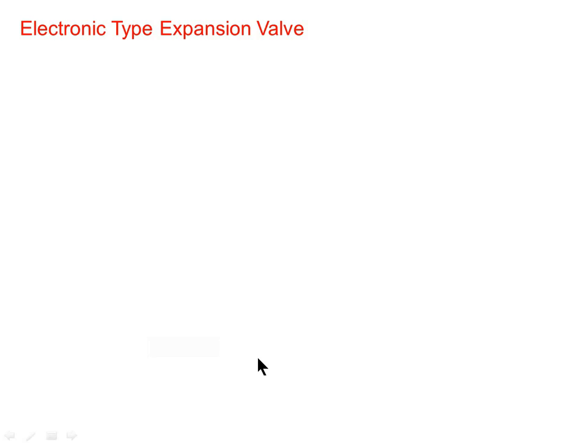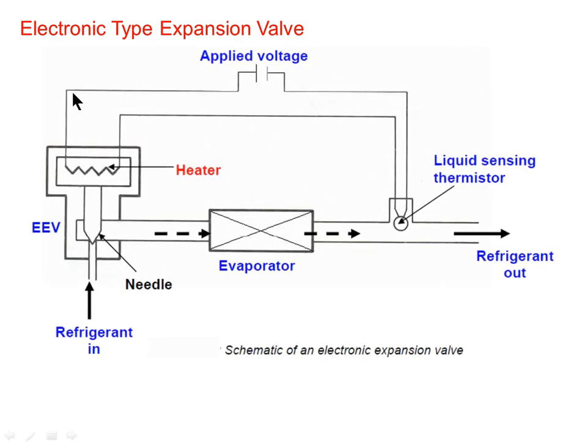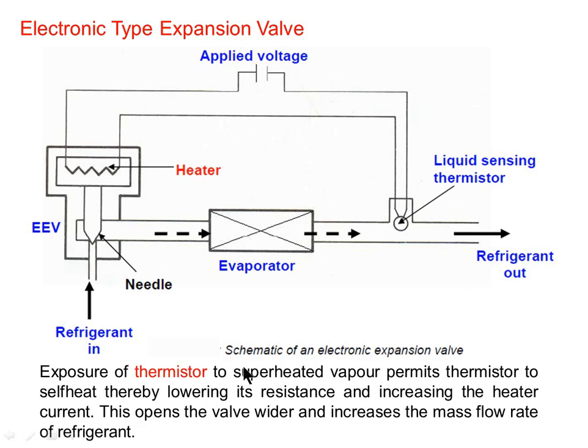Next is the electronic type of expansion valve. The diagram shows the refrigerant inlet, needle, electronic expansion valve, heater, liquid sensing thermistor, evaporator, and refrigerant outlet. Exposure of the thermistor to superheated vapor permits the thermistor to self-heat, thereby lowering its resistance and increasing the heater current. This opens the valve wider and increases the mass flow rate of refrigerant. In this way, the flow through the electronic expansion valve is maintained.